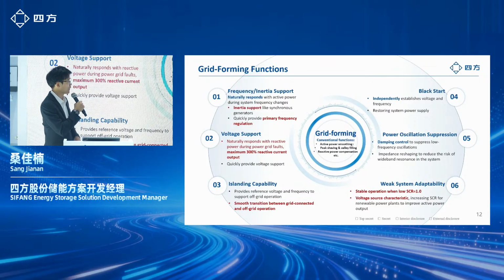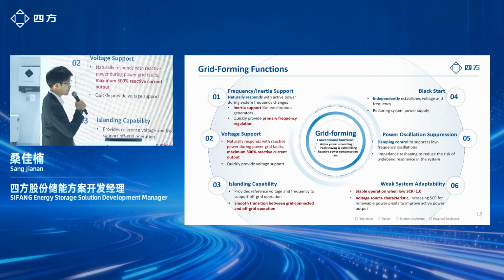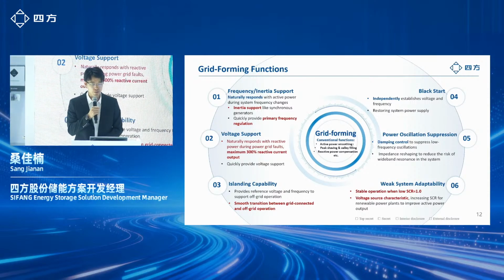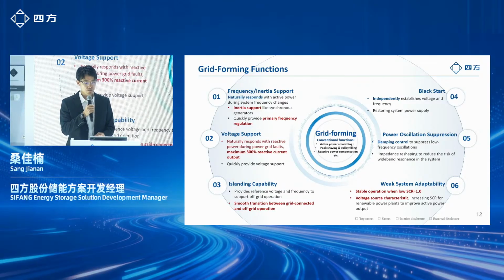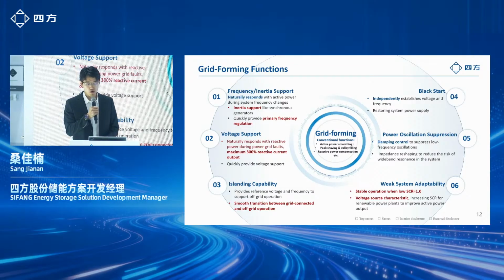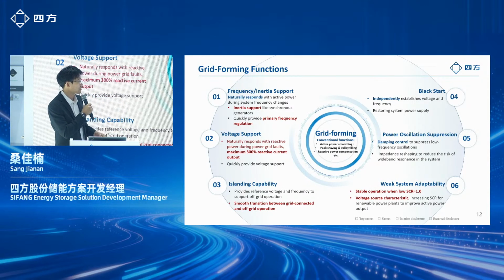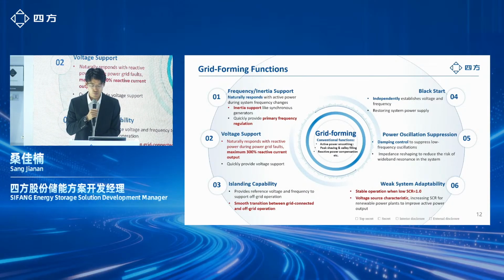And here are the functions of the grid-forming technologies. First, frequency and inertia support, which means it quickly provides frequency regulation and inertia support to the grid. Then voltage support. It can also output a maximum 300% overload current. Then islanding capability and black start, independently establishing the voltage and frequency. The fifth one is power oscillation suppression, which means it performs damping control to suppress low frequency oscillation. And the last one, it can operate at low SCR.